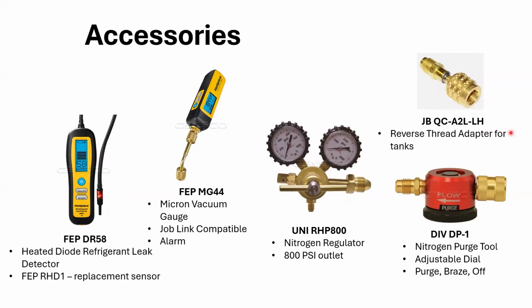Here are the reverse thread adapters for the refrigerant recovery tanks and the refrigerant tanks. Reverse thread, right? So you're going to need some of those. Get more than one, right? Because one's going to be lost or missing, and you'll be stuck without it. So, a purge device for brazing, pressure testing, etc.